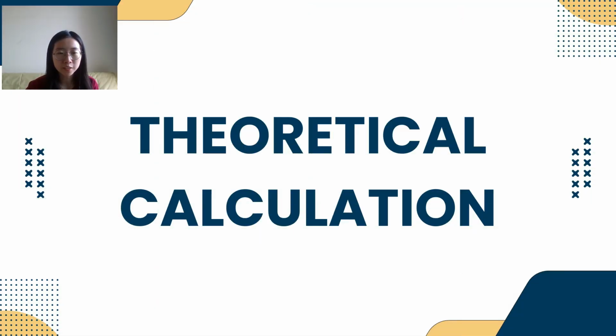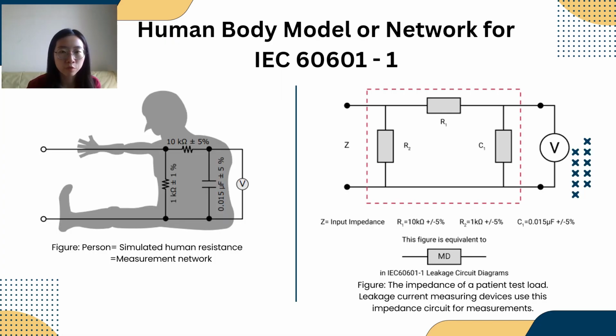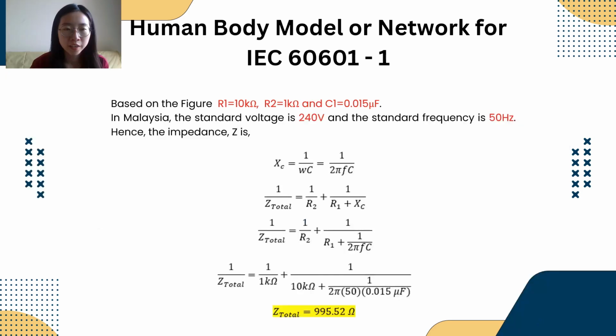Good morning, Doctor. I am Ophelia. So now I would like to present the theoretical calculation. These two figures show the human body model for IEC 60601-1. Here is the circuit, showing the Z input impedance. R1 equals 10 kilo ohm, R2 is 1 kilo ohm, and C1 is 0.015 microfarad. All of it is plus minus 5% of error. In Malaysia, the standard voltage is 240 volt, and the standard frequency is 50 Hz. Hence, we can calculate the impedance Z as below. We get Z total equal to 995.52 ohm.